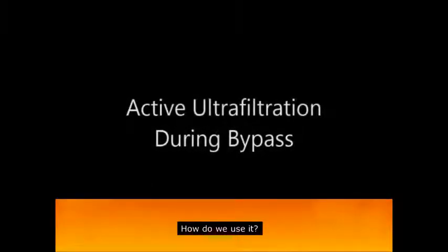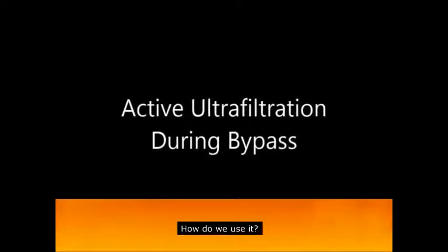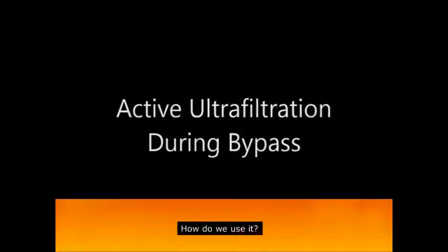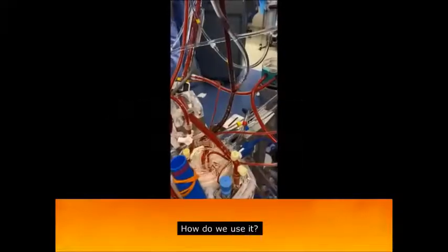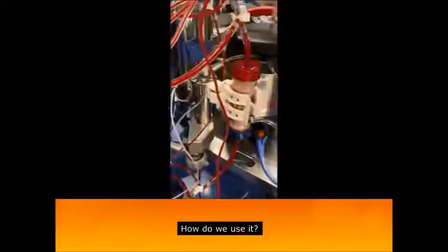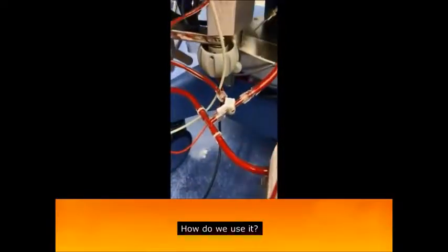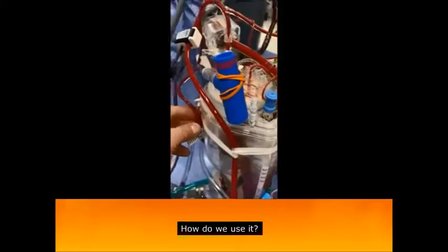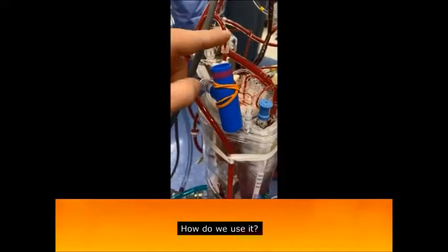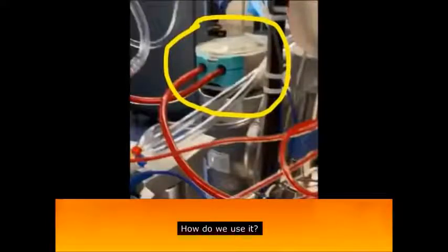Transitioning to ultrafiltration during bypass, this quick video shows active conventional ultrafiltration with the same blood flow path as that which was used for PBUF. Active ultrafiltration can be performed at any time during bypass. The flow path is the same as that which was used during pre-bypass ultrafiltration, running from the venous line to the ultrafilter head, to the top of the hemoconcentrator, to the bottom, and then back to the venous reservoir. The ultrafiltration head is simply turned on as needed.